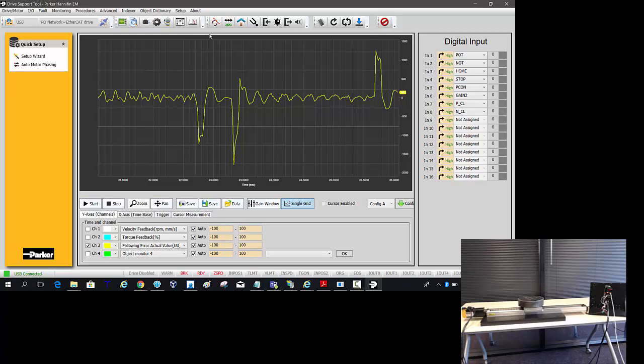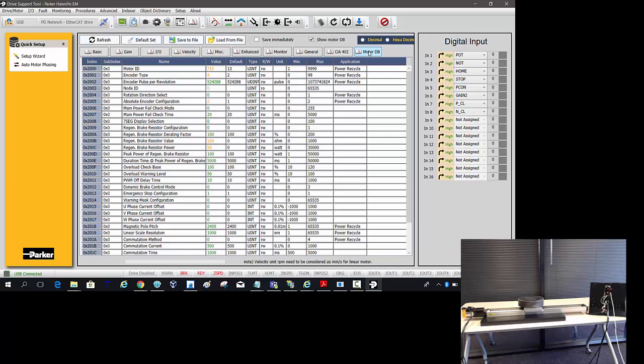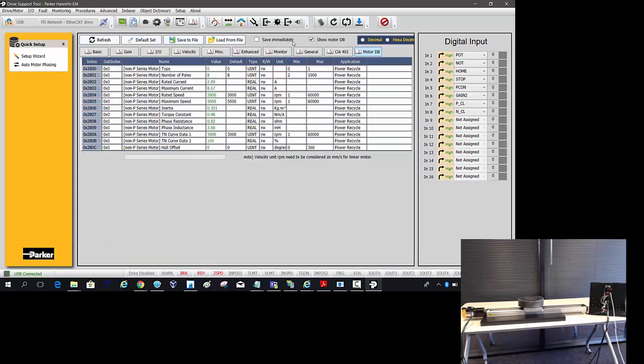And then if you want to create a backup copy of this to duplicate into another drive, I know I've covered this in another video, but if we go into the object dictionary, you can show motor database. The P-Series motors are already detected on the P-Series drives. This would only be needed if you had a BE or an MPP or an SM-Series motor, neometric J-Series, or a linear motor as well. The show motor database will include the motor information. And then if you want to save to file, name that anything that you want.